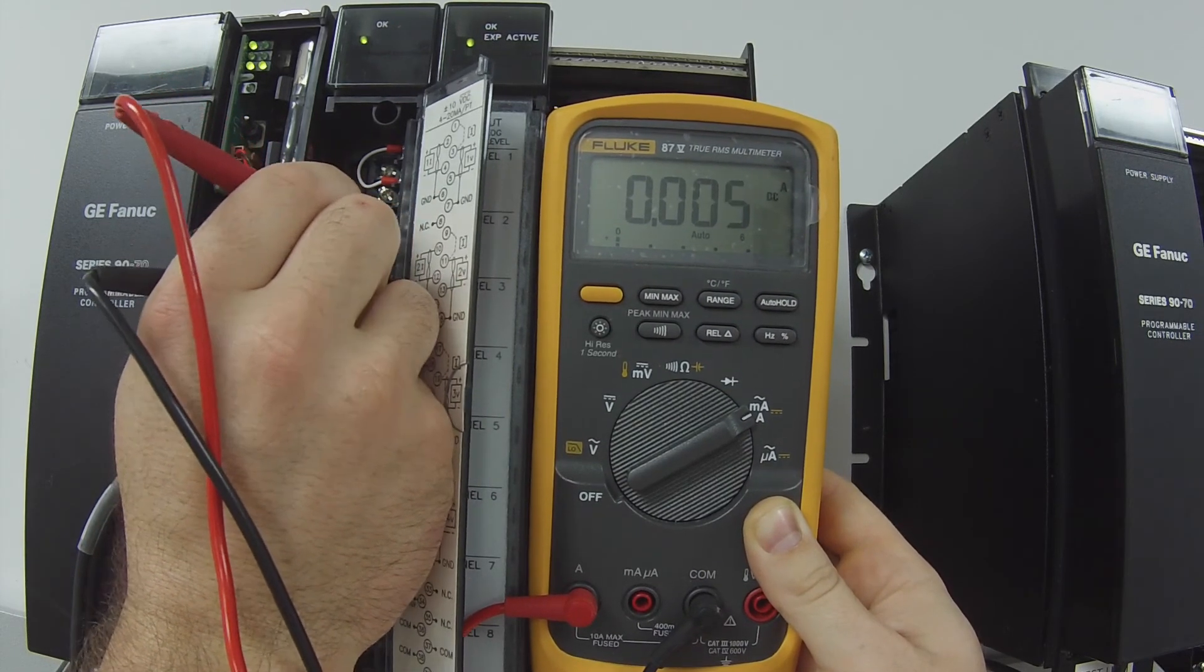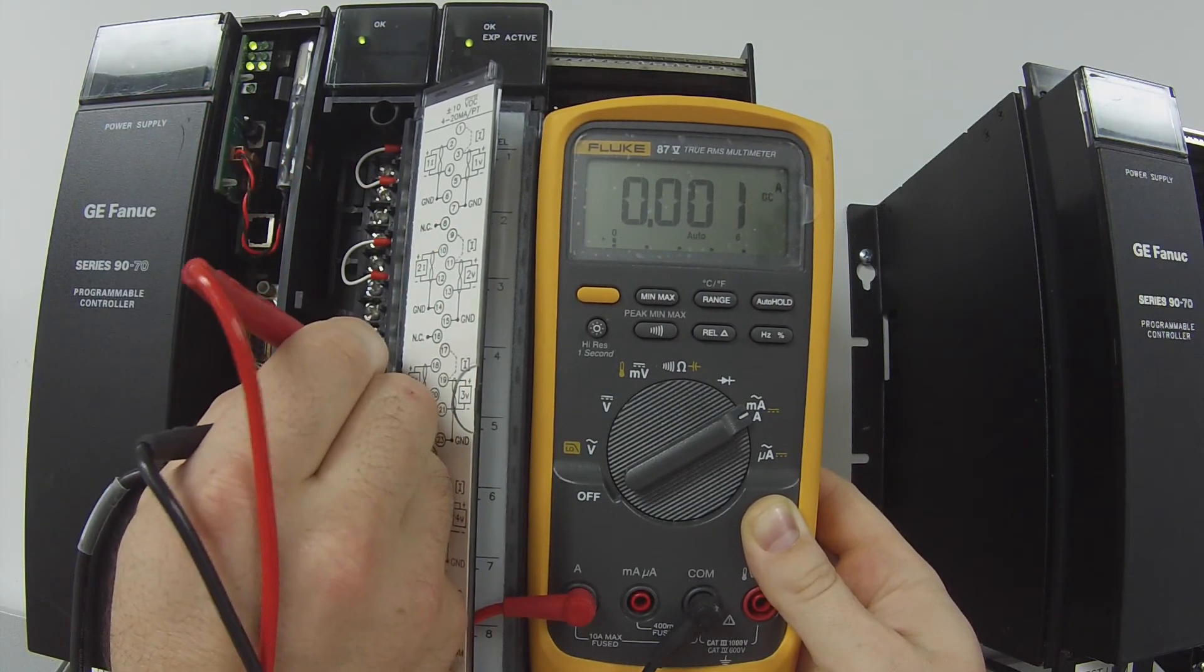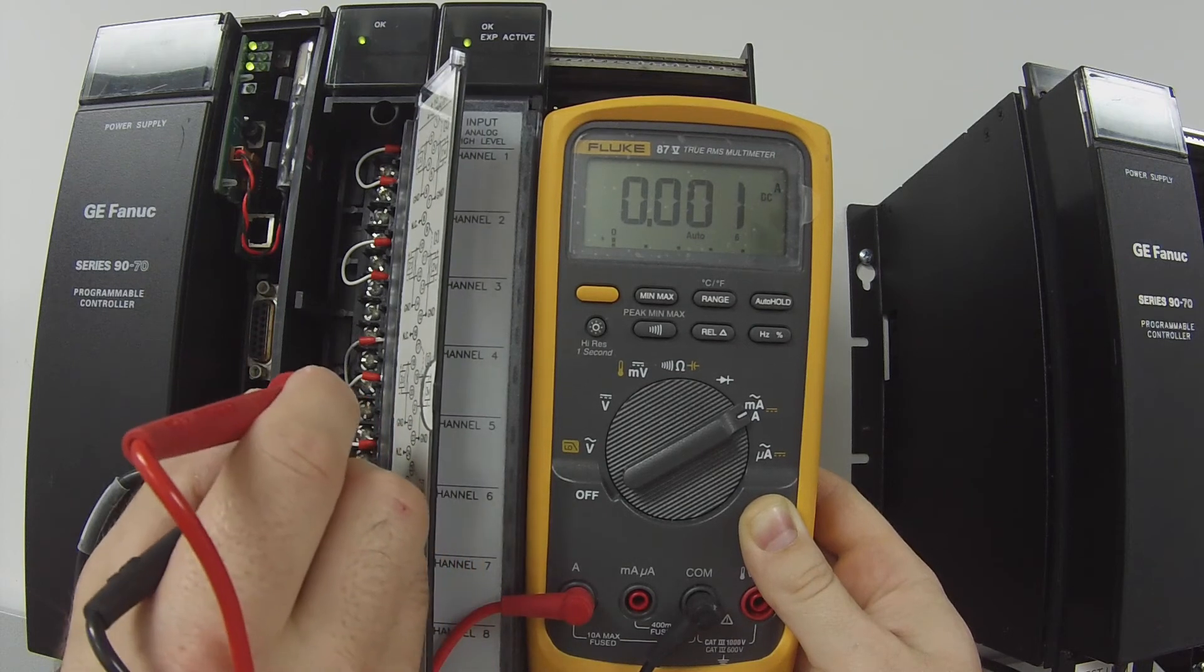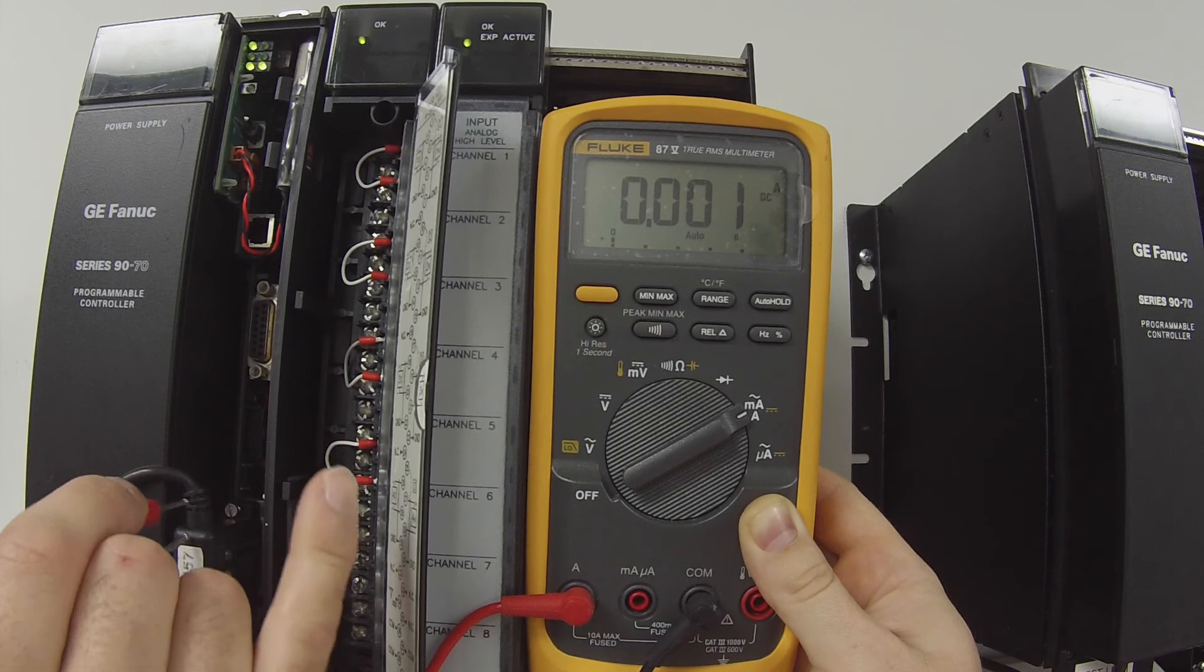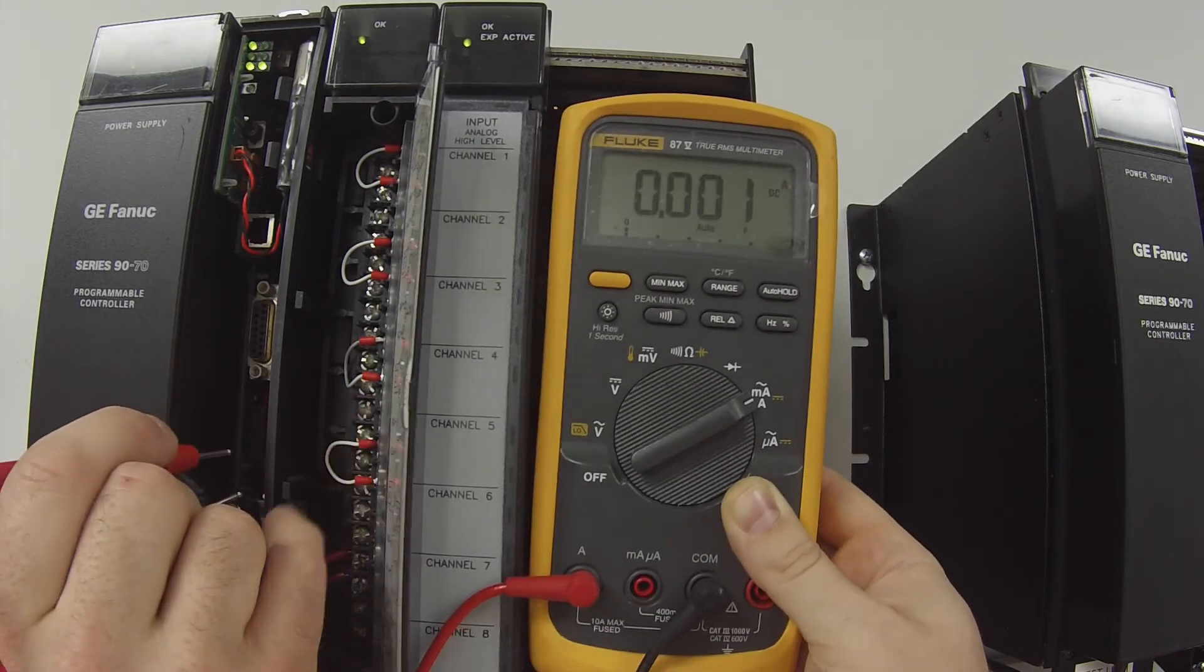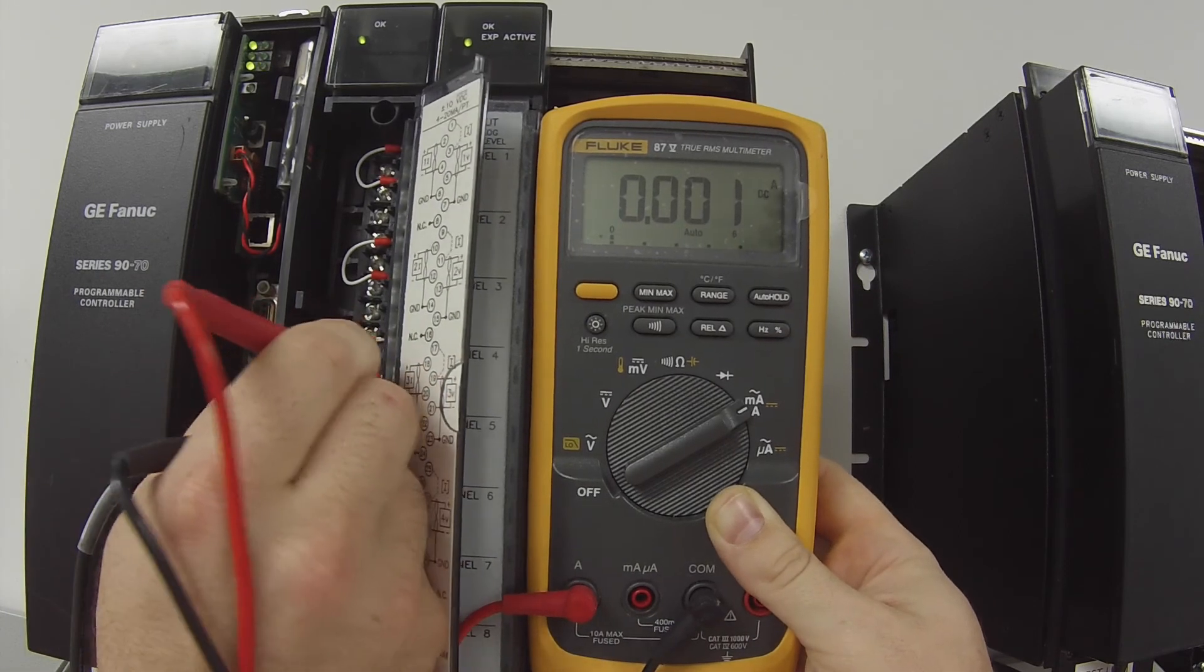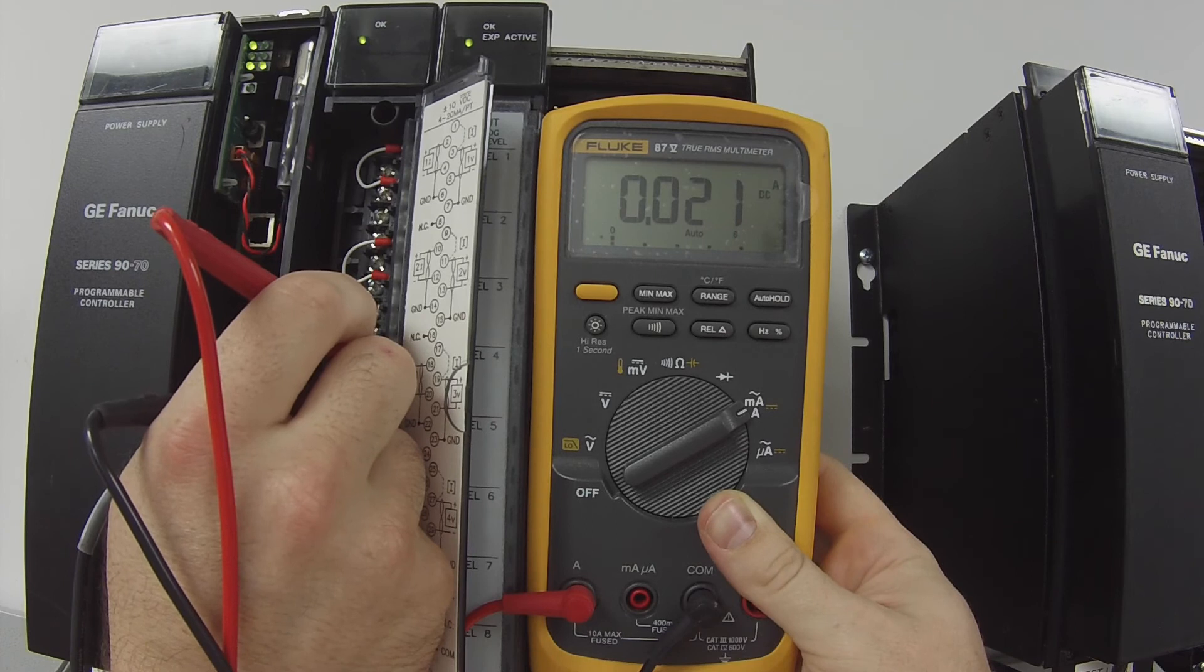I like to zero it out because if it does fail, it's going to fail at full value, the full 20 milliamps typically. Output number 3, we're looking for terminals 18 and 20. There we go. And then we dropped it.